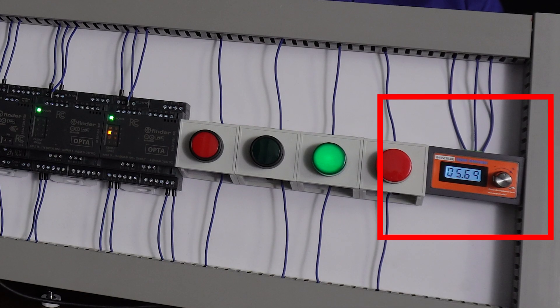Here I wrote a temperature control program for the control cabinet using a ventilator and a heater. At the beginning I performed the scaling of the analog value. Here we can connect the temperature sensor value to this function block. Instead of a temperature sensor I have a voltage regulator for educational purposes. At the output of this function block I get a real type value — a floating point variable.